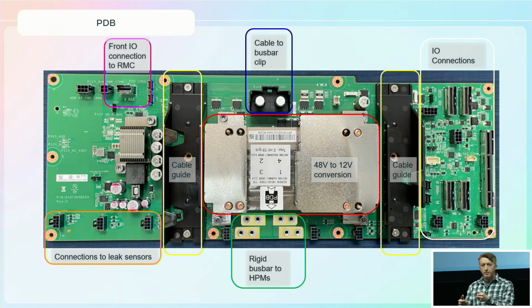To get the high power to the HPMs, the highest-powered components in the tray, we use a rigid bus bar. You can see in the green box, middle of the board, these are rigid, thick bus bars that you clamp in at the correct torque. That gets us successful power delivery and meets the PDN delivery requirement.